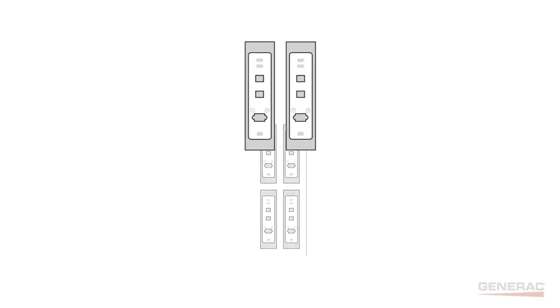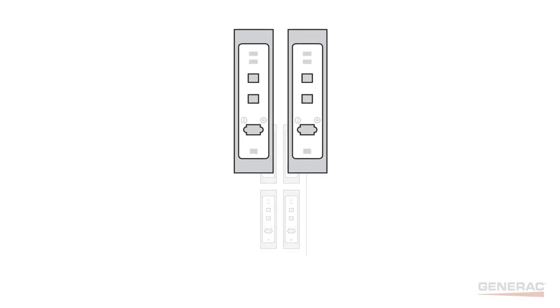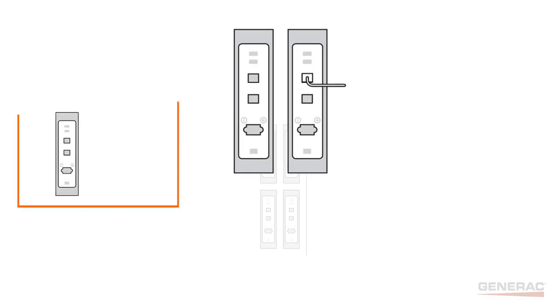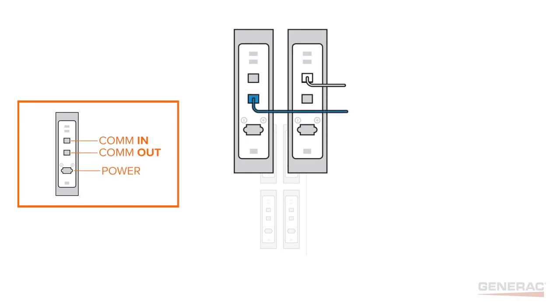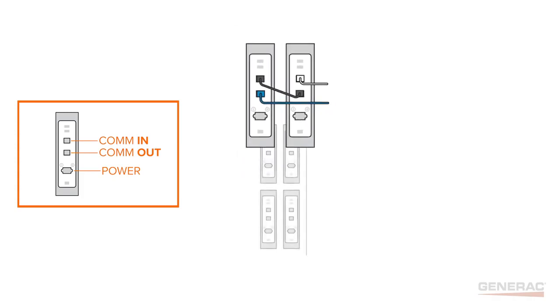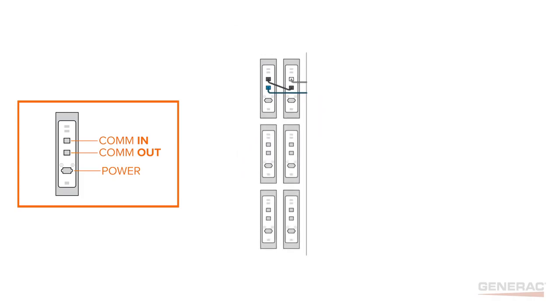Starting with the topmost rear battery module, install the gray Ethernet-style cable to the COM-IN port. Then, on the topmost front battery, install the blue Ethernet-style cable to the COM-OUT port. This leaves the COM-OUT port on the rear battery and the COM-IN port on the front battery both open. This is where we'll install one of the black Ethernet jumper cables. The Ethernet jumper cables will always go from the COM-OUT port on the rear battery to the COM-IN port of the front battery of any given shelf.